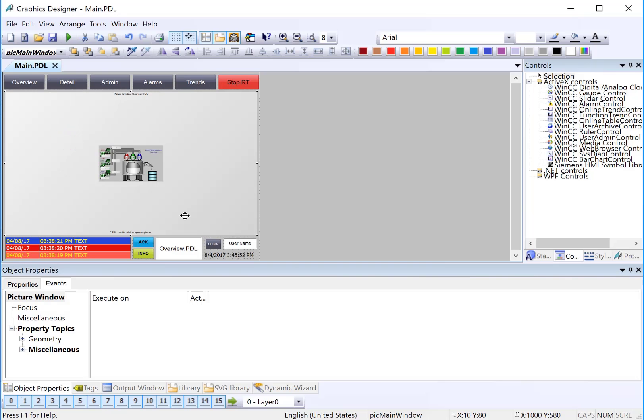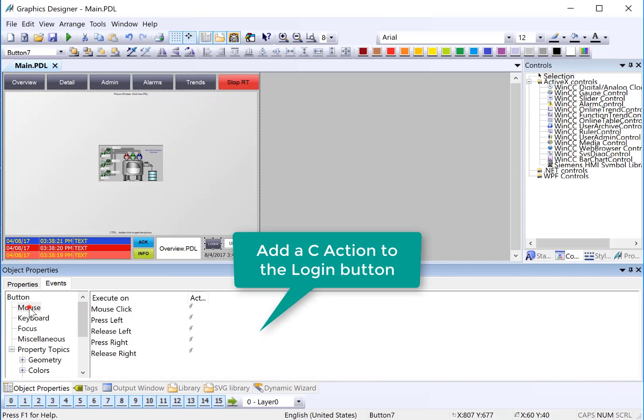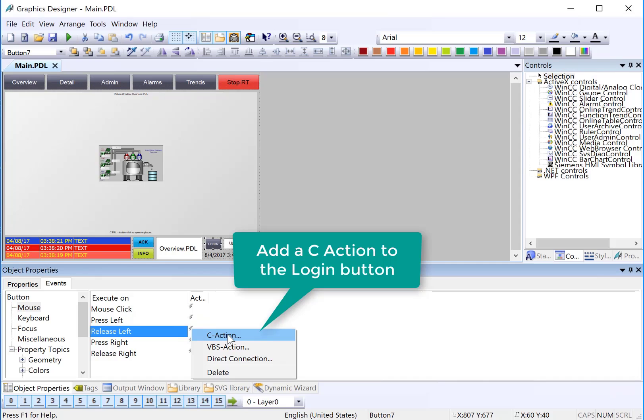On the main PDL, we need to configure the login button to show the logon dialog when it's clicked. To do this, we'll select the button, select the events tab, mouse, and we'll do the release left dynamic. And we're going to add a C action.